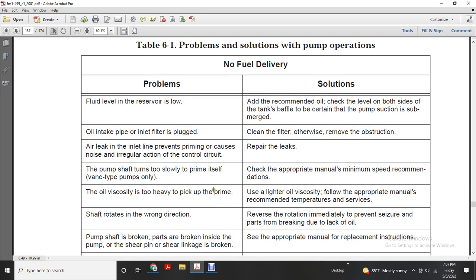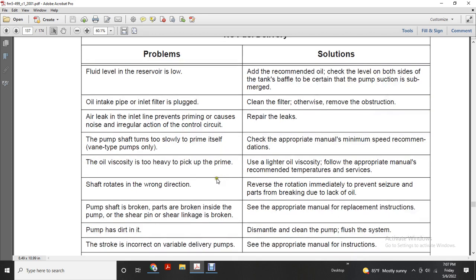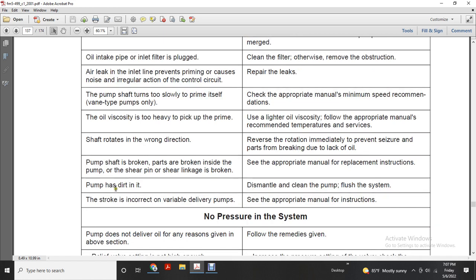The oil viscosity is too heavy to pick up: use light oil viscosity. Follow the appropriate manual's recommended temperatures and service. Shaft rotates in the wrong direction: reverse the rotation immediately to prevent seizure and parts breaking due to lack of oil. Pump shaft is broken, parts are broken inside the pump, or a shear pin or linkage is broken: see the appropriate manual for replacement instructions. Pump has dirt in it: dismantle, clean the pump, and flush the system. The stroke is incorrect on a variable delivery pump.